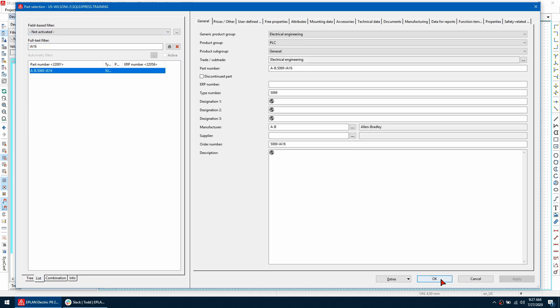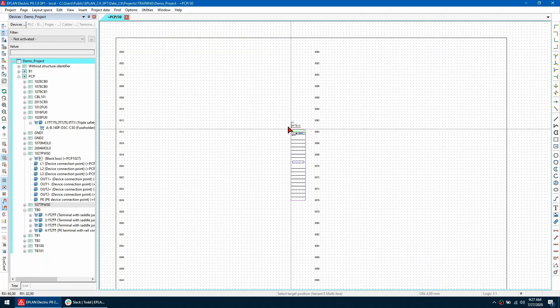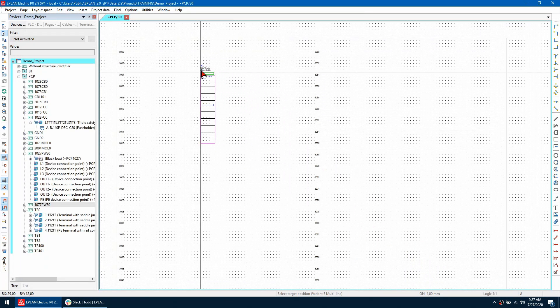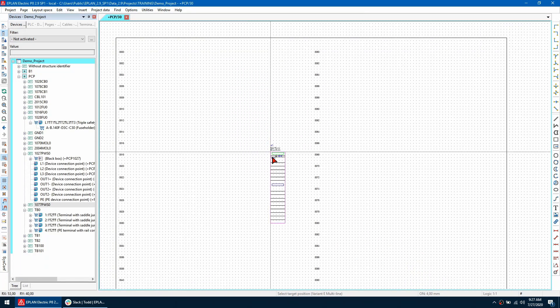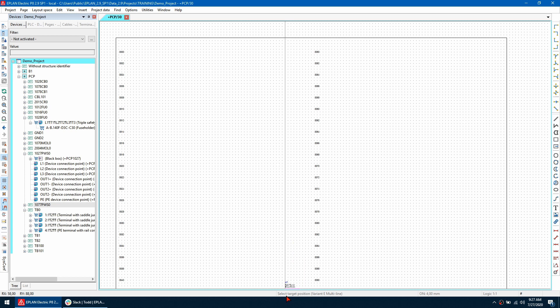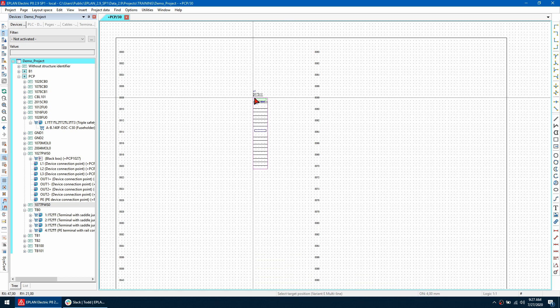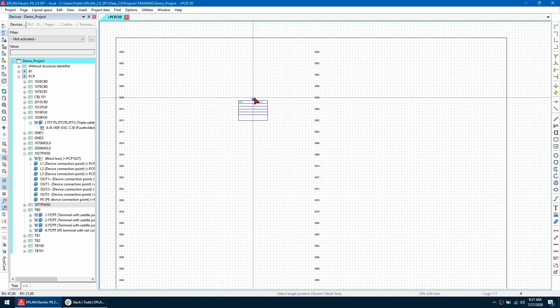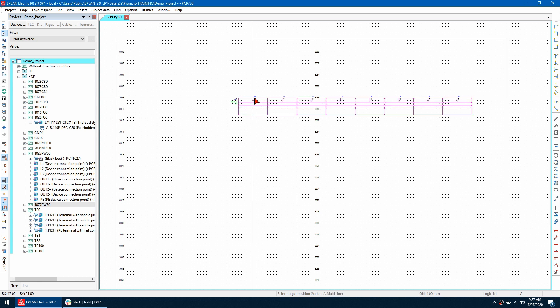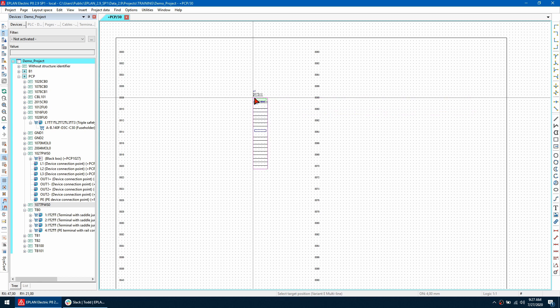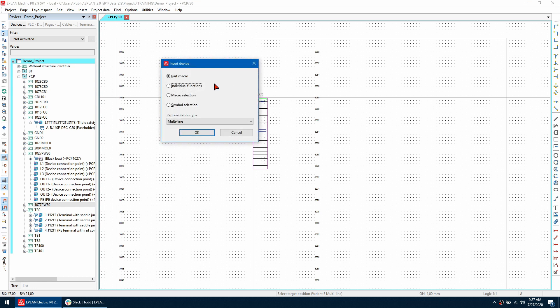So I'm placing it in my schematic I can see that ePlan is prompting me and telling me to use variant E. If I hit the tab key I can cycle through all the different variants so here is variant I and then back to A, B and then finally back to E. So if I don't want to use any of these variants I can hit the backspace key and then select individual functions.